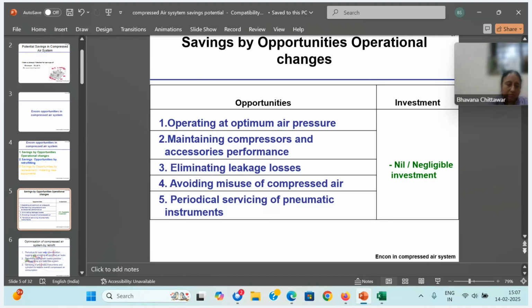Once you optimize air pressure, you will get double savings. One at compressor power. Second, your overall consumption also will come down. If you operate at lower pressure, your consumption will come down drastically. So there is potential. If you reduce the air pressure setting by 1 kg, you can achieve 6 plus 6, that is 12% minimum savings, directly. Indirectly, it will reduce wear and tear, temperature rise, and maintenance cost as well. Then, maintaining compressor and accessories performance.